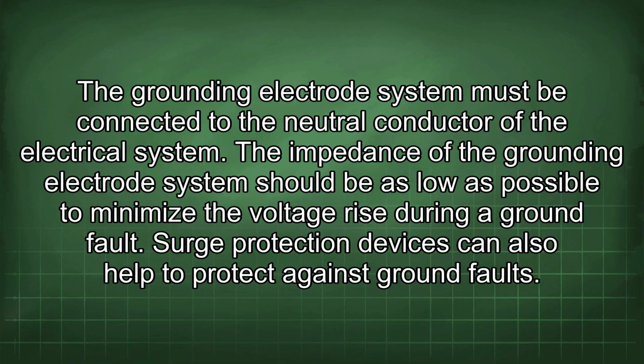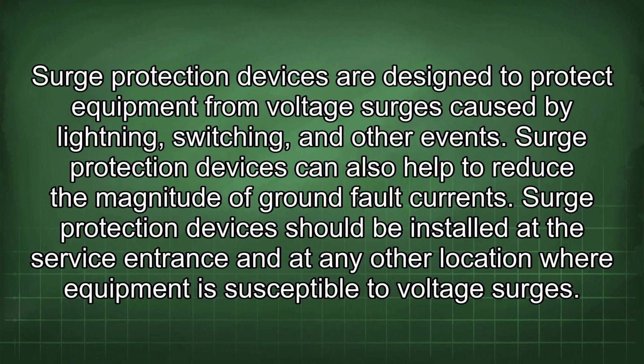The impedance of the grounding electrode system should be as low as possible to minimize the voltage rise during a ground fault. Surge protection devices can also help to protect against ground faults. Surge protection devices are designed to protect equipment from voltage surges caused by lightning, switching, and other events. Surge protection devices can also help to reduce the magnitude of ground fault currents.